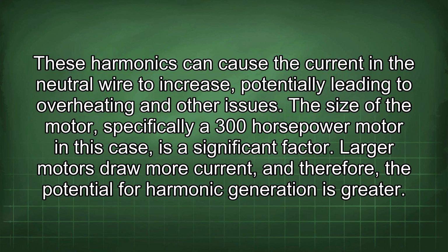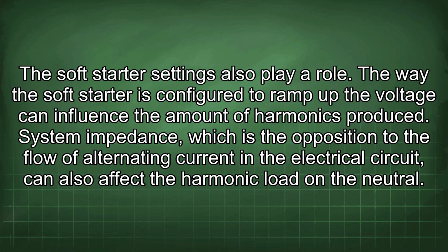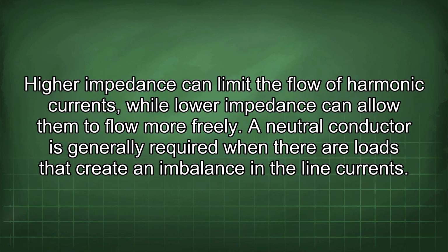The size of the motor, specifically a 300 horsepower motor in this case, is a significant factor. Larger motors draw more current, and therefore the potential for harmonic generation is greater. The soft starter settings also play a role. The way the soft starter is configured to ramp up the voltage can influence the amount of harmonics produced. System impedance, which is the opposition to the flow of alternating current in the electrical circuit, can also affect the harmonic load on the neutral. Higher impedance can limit the flow of harmonic currents, while lower impedance can allow them to flow more freely.